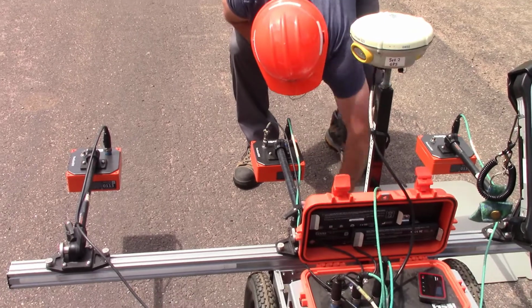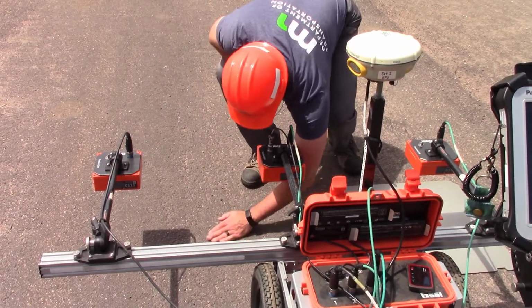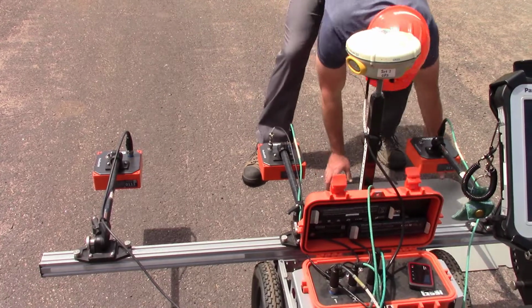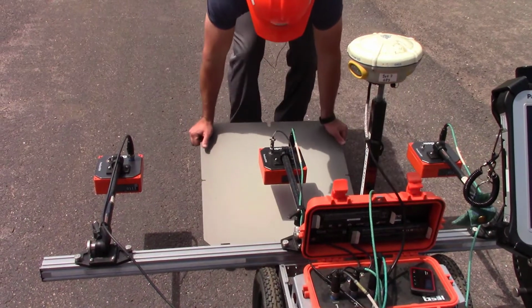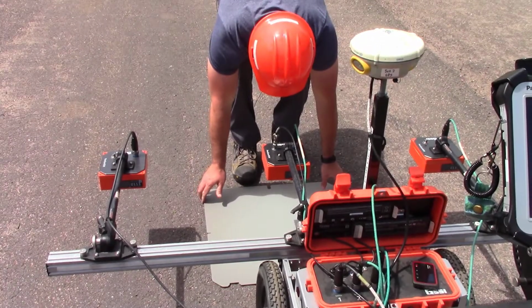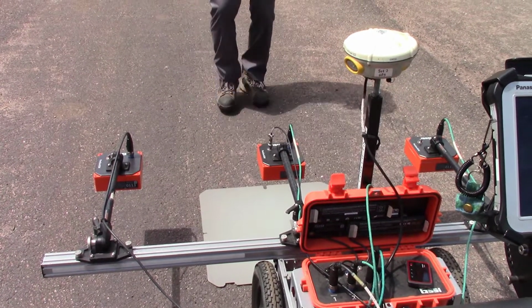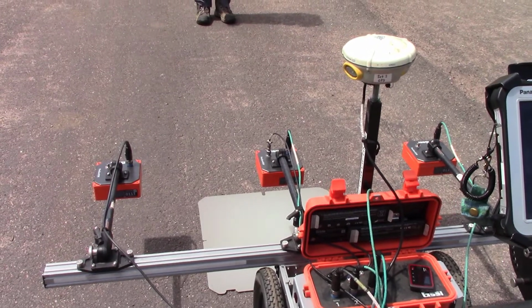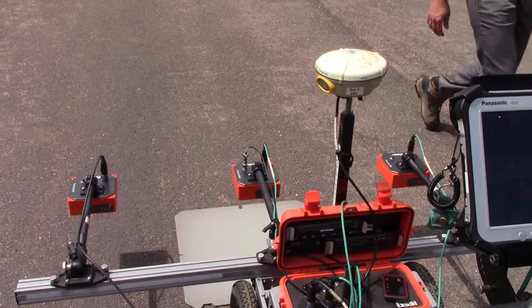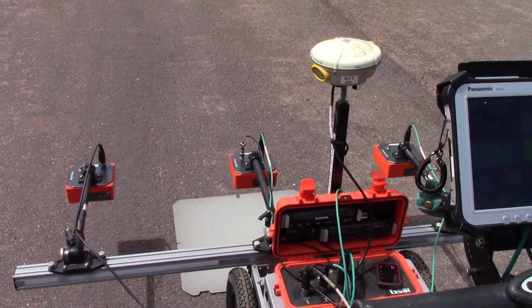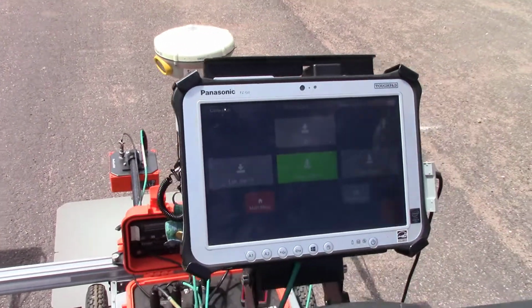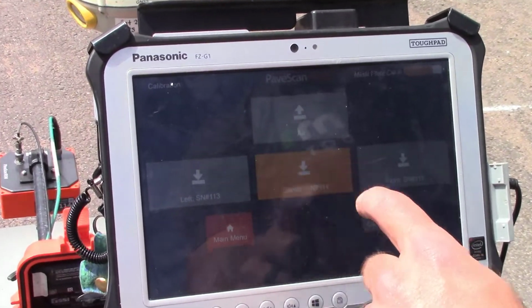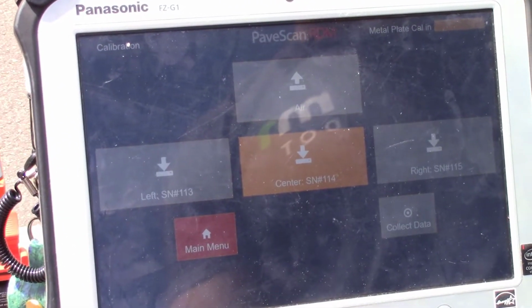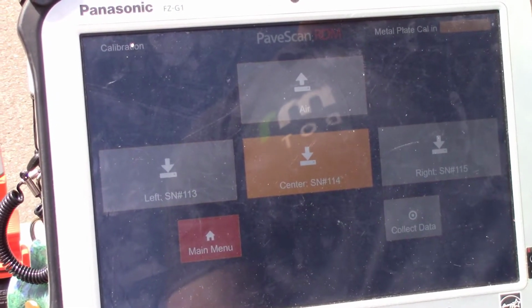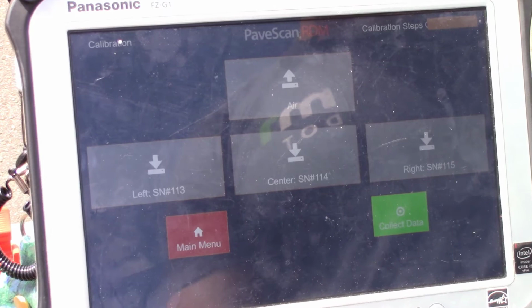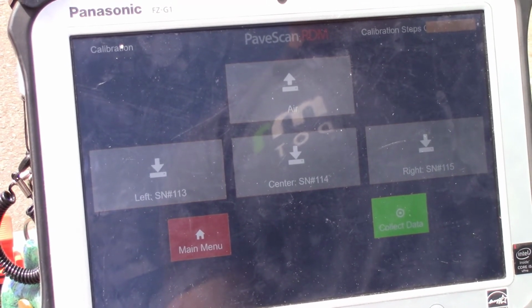So for our center sensor, the process is exactly the same. You're going to want to remove anything that would make your metal plate not sit flush to the surface. And you're going to want to center your plate in both the lateral and longitudinal direction. And once you're happy, you'll press the corresponding green button. In this case, that's our center sensor. Now you've successfully completed calibration of your sensors.